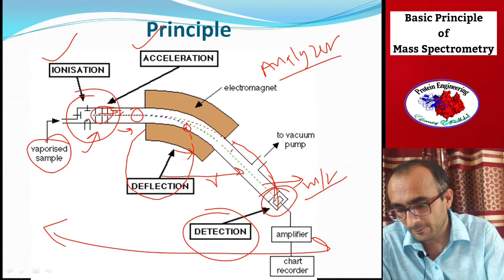So in order to collect, then what will happen? This blue beam will collide with the wall of the analyzer and it will get neutralized. This whole system is kept at very high vacuum pressure, 10⁻⁷ to 10⁻⁸ millibar. Because of the high vacuum pressure, the ions which collide with the wall of the analyzer are removed from the system.